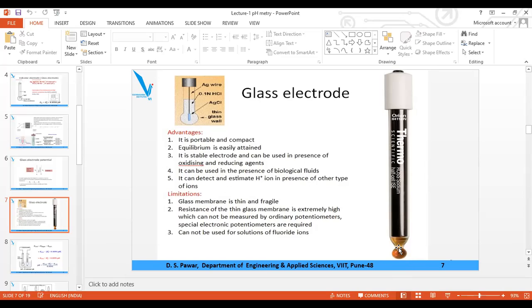So utmost care needs to be taken when you are using it in the solution. Otherwise, if you don't want to break this, then use another glass rod for stirring the solution. Remove the electrode from the solution and stir it with the help of a glass rod, so you can protect the bulb from breaking, because it is very fragile. It also cannot be used in the presence of fluoride ions, because the glass electrode responds in the negative sense to fluoride ion. So these are the two disadvantages.